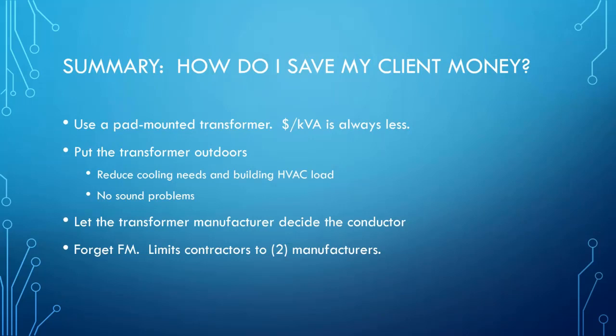Some additional reasons to put the pad mounted transformer outside: you reduce your HVAC load. Regardless of how efficient the transformer is going to be, it is going to emit heat, and that heat must be removed. Another reason is the sound. Occasionally we hear people complaining about the sound. This is more dry type than liquid filled, really, but that's something you kind of take off the table. You don't have to worry about it.